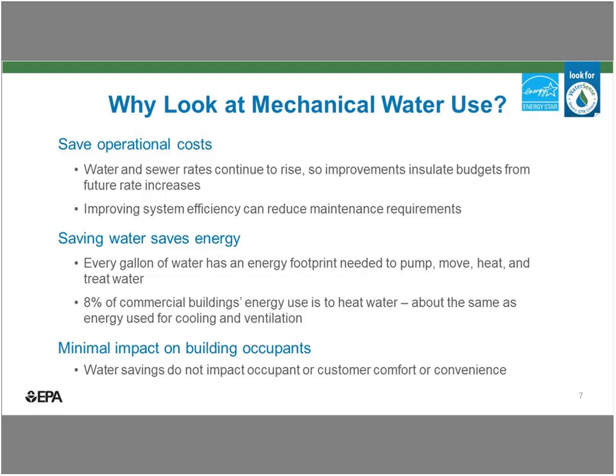And in general, just beyond the mechanical spaces in your building, finding ways to reduce hot water use, whether that be in a boiler or plumbing fixtures or commercial kitchens, those usually will have a commensurate water savings as well. And lastly, saving water in your mechanical rooms tends to be a little bit of a behind-the-scenes conservation effort. So sometimes facility managers or buildings may be a bit hesitant to implement efficiency in more occupant-facing or visitor-facing areas like restrooms or landscapes, because there may be backlash or fear that there might be negative feedback from occupants or customers. Mechanical improvements kind of provide this behind-the-scenes opportunity for savings where occupants won't necessarily feel the impact of that.